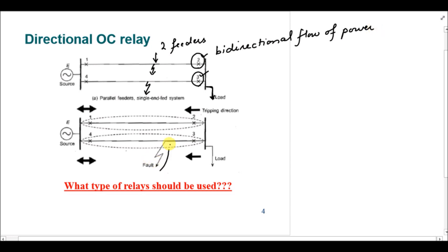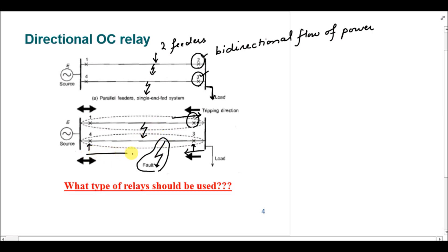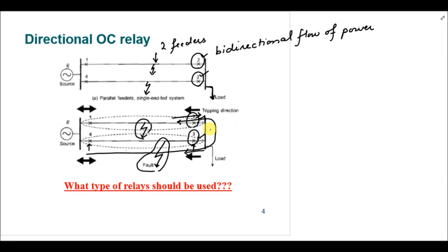For example, if there is a fault in the second line bounded by circuit breakers three and four, the fault power is moving away from the bus for breaker three so it should operate, but for breaker two the fault power is moving towards the bus so it should not operate. Similarly, for a fault in the other feeder, breaker three sees power moving towards the bus and should not operate, while breaker two sees power moving away and should operate. Therefore, circuit breakers two and three should be attached to directional overcurrent relays to correctly identify faults in parallel feeders.